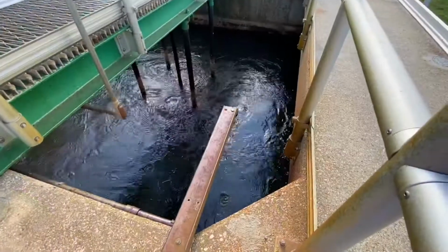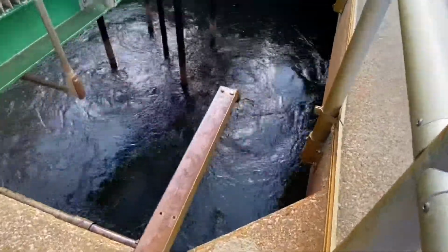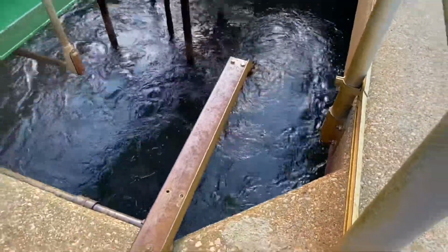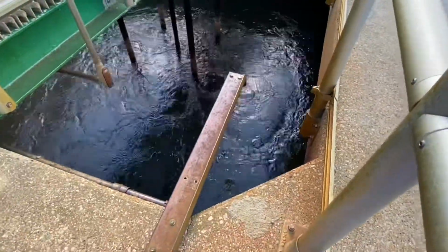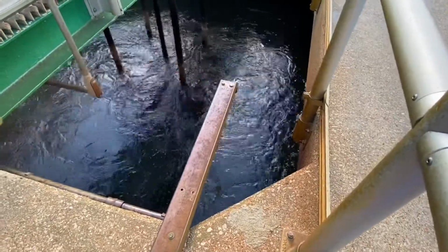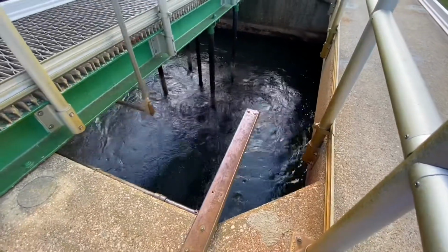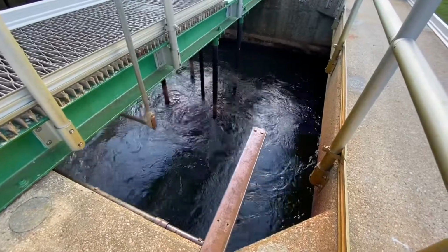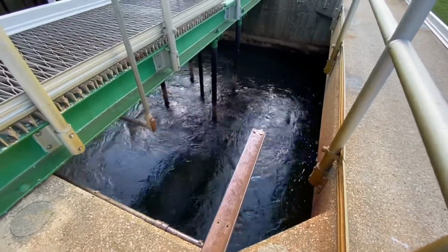I'm standing on a flocculation basin, and this is where the chemical addition and treatment takes place. So let's take a closer look at this process. The water exits the treatment process and enters into the flocculation basin. And here we are adding a metal salt. Some plants may use alum, aluminum salts, or iron salts, ferric. We use ferric chloride. The ferric chloride has a positive charge and gets flash mixed throughout the entire basin so that it will bond to the negatively charged phosphate ions.